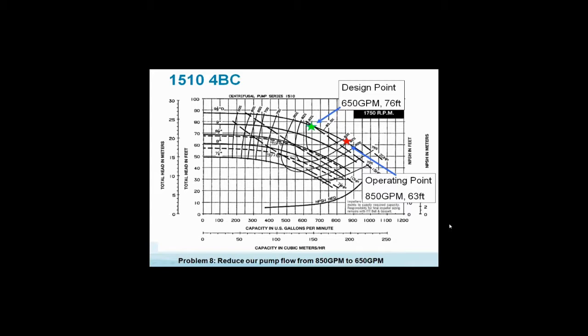I have a 9.5-inch pump impeller. So when I go to the left-hand column where my 63 feet of head is, and run a line straight across to my pump impeller, which is where the red star is, I wind up with 63 feet of head and I'm flowing 850 GPM. My design was 650 GPM at 76 feet of head. The system will work, but it's going to use a lot of extra brake horsepower. You may have some zones that are noisy; the velocity is so high it may be a problem.